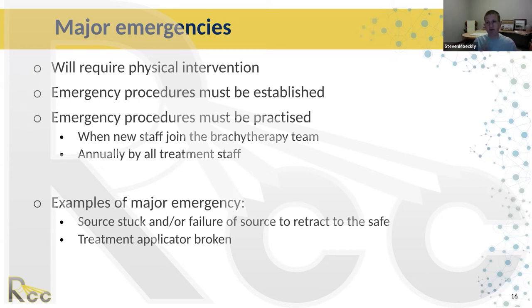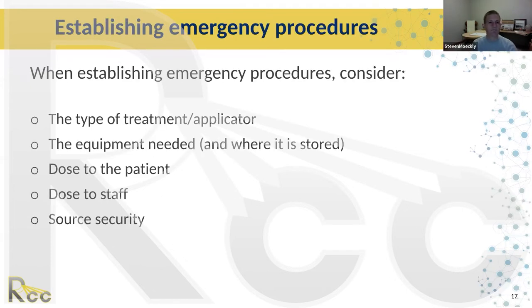A broken applicator is probably one of the most realistic major emergency situations. If a doctor inserts an applicator under torque or pressure and it cracks, and during treatment it dislodges further, that could result in the source being unable to retract. That's a good scenario to drill. When establishing emergency procedures, you need to consider the type of treatment and applicator — certain procedures might work for a tandem and ovoid but not for a tandem and ring.